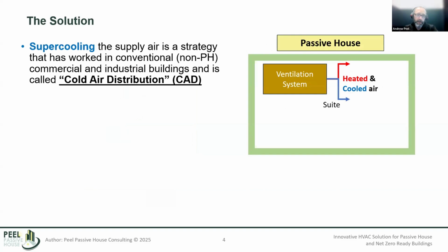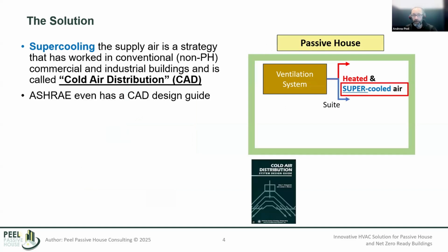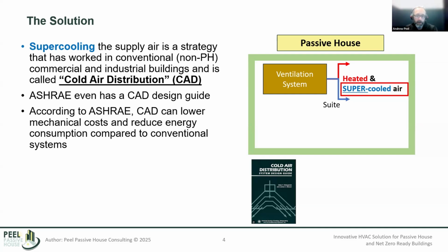So what we're proposing is to implement a strategy called cold air distribution. This is actually a strategy from the commercial and industrial building sectors that's been successfully applied—ASHRAE even has a design guide on cold air distribution. This essentially means supercooling our supply air, which in this case is our ventilation air. I could speak for hours about this background, so for brevity I've taken some of it out, but essentially according to ASHRAE, cold air distribution can lower mechanical costs and reduce energy consumption.